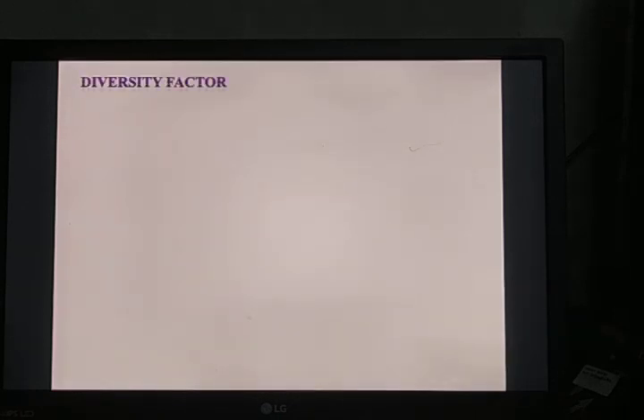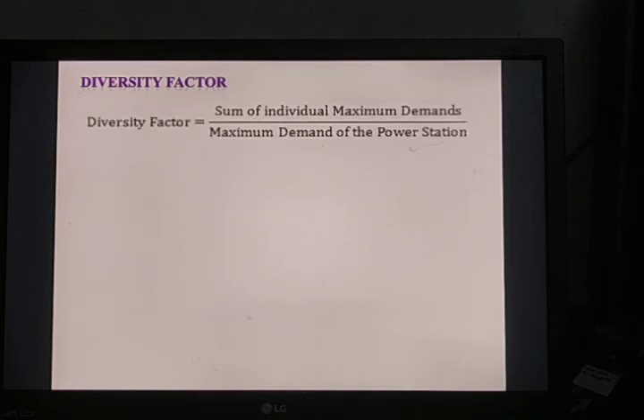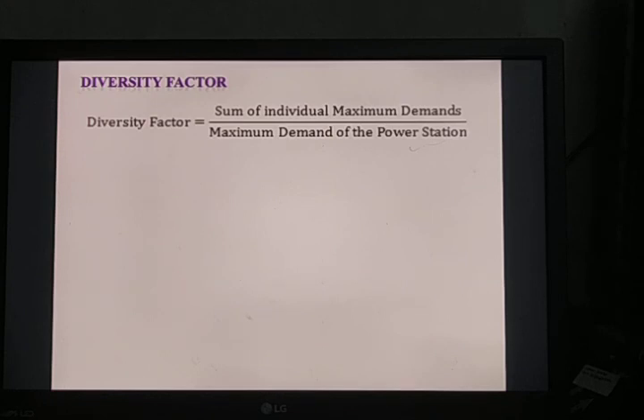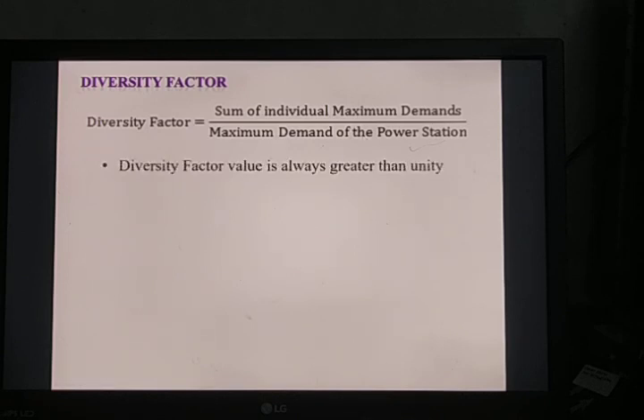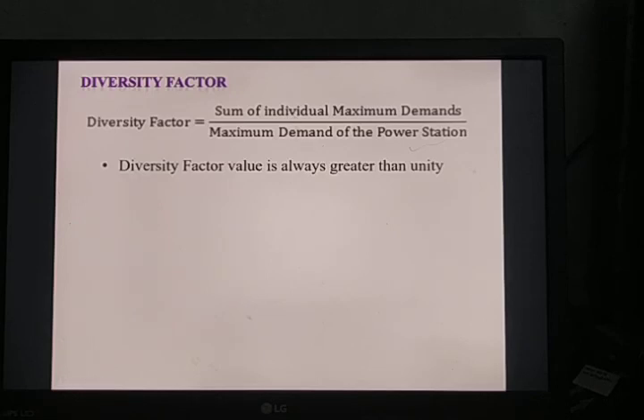Diversity factor is defined as the ratio of the sum of individual maximum demands of all consumers to the maximum demand on the power station. A power station is connected to various types of consumers — domestic load, industrial load, and so on — and these loads are different. The sum of all individual maximum demands divided by the maximum demand on the station gives the diversity factor. Diversity factor is always greater than 1, because the maximum demand on the power station is always less than the sum of individual maximum demands.